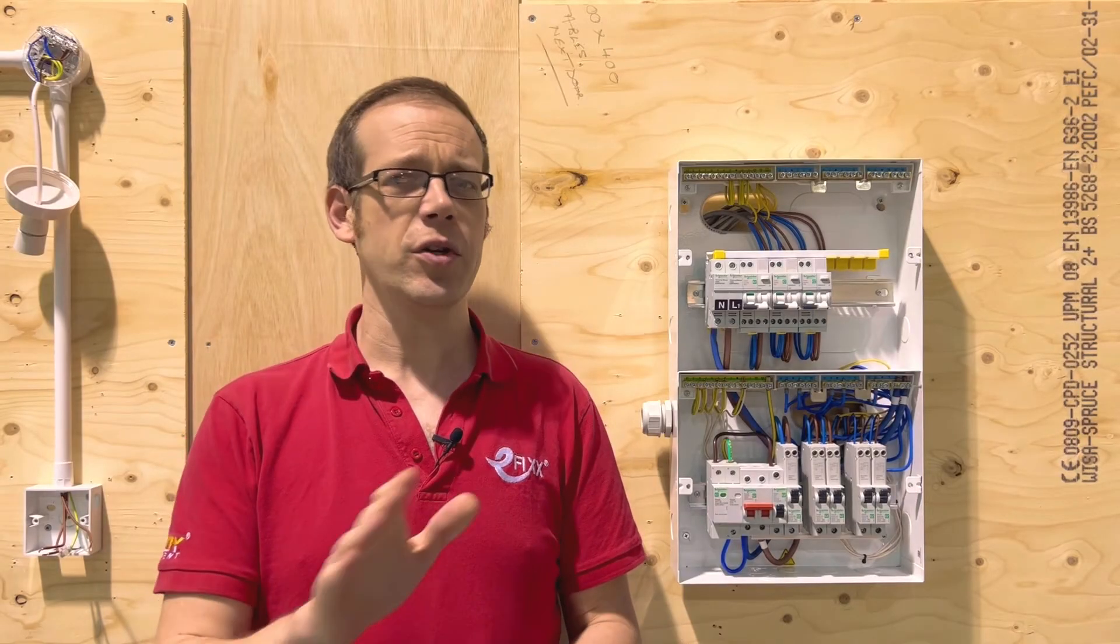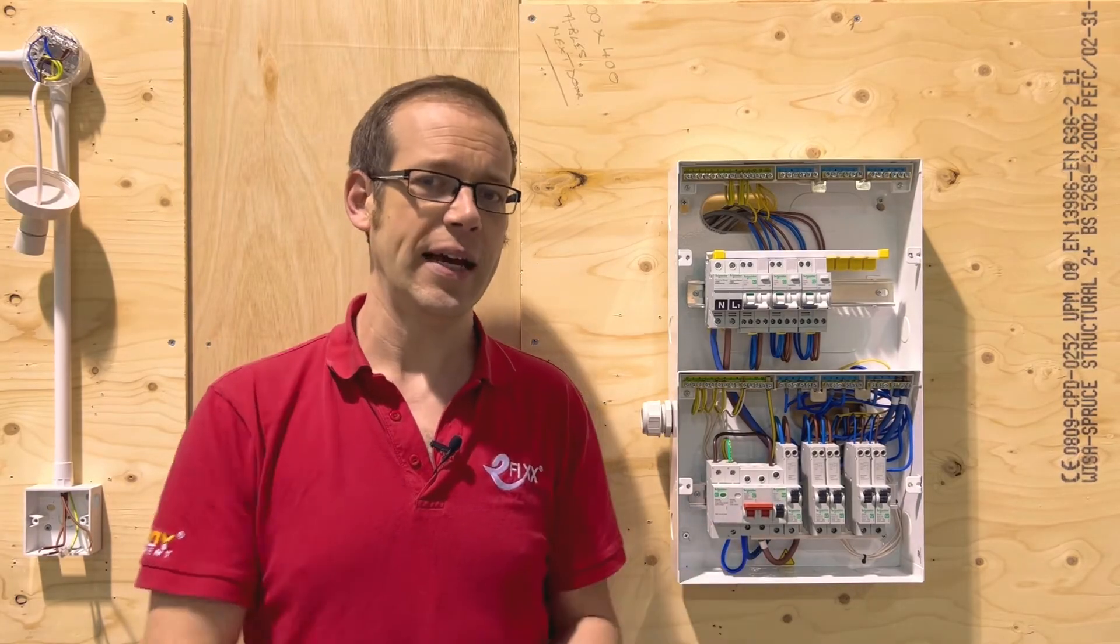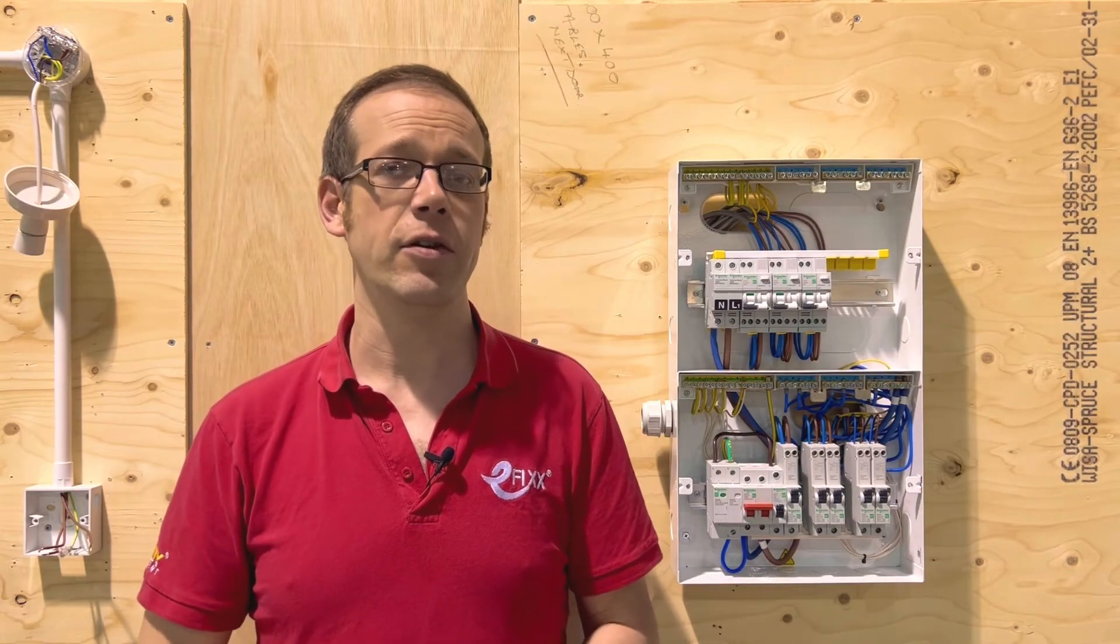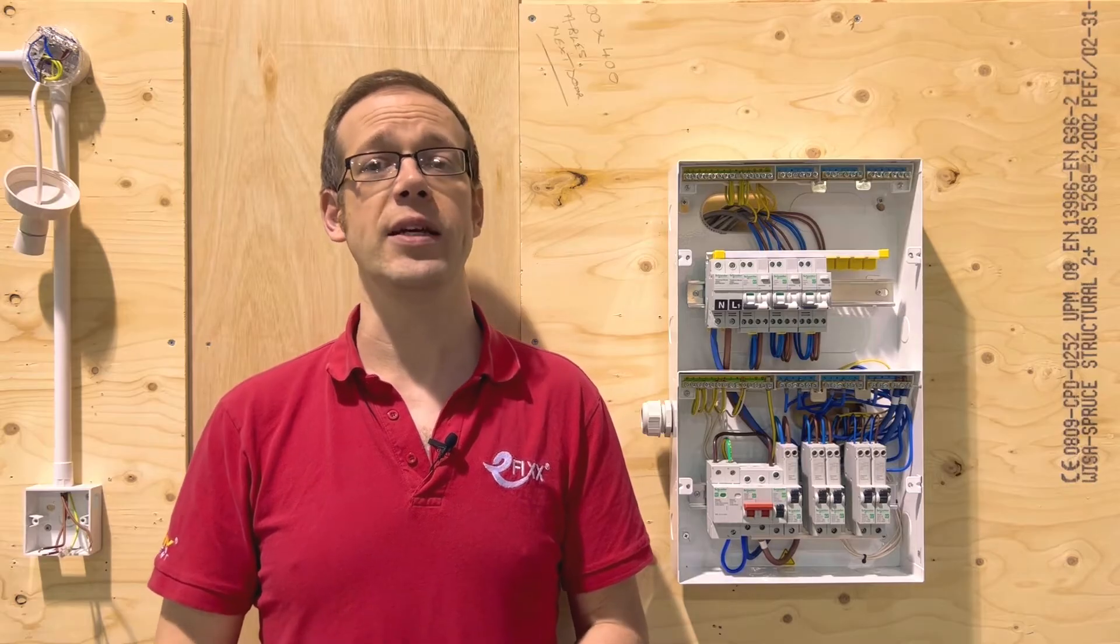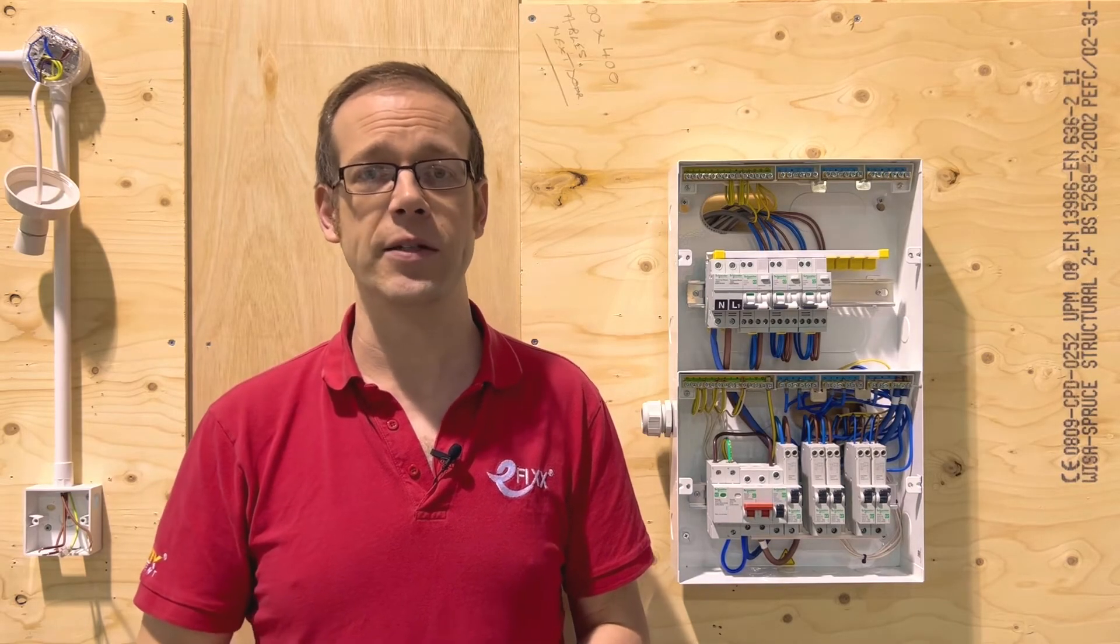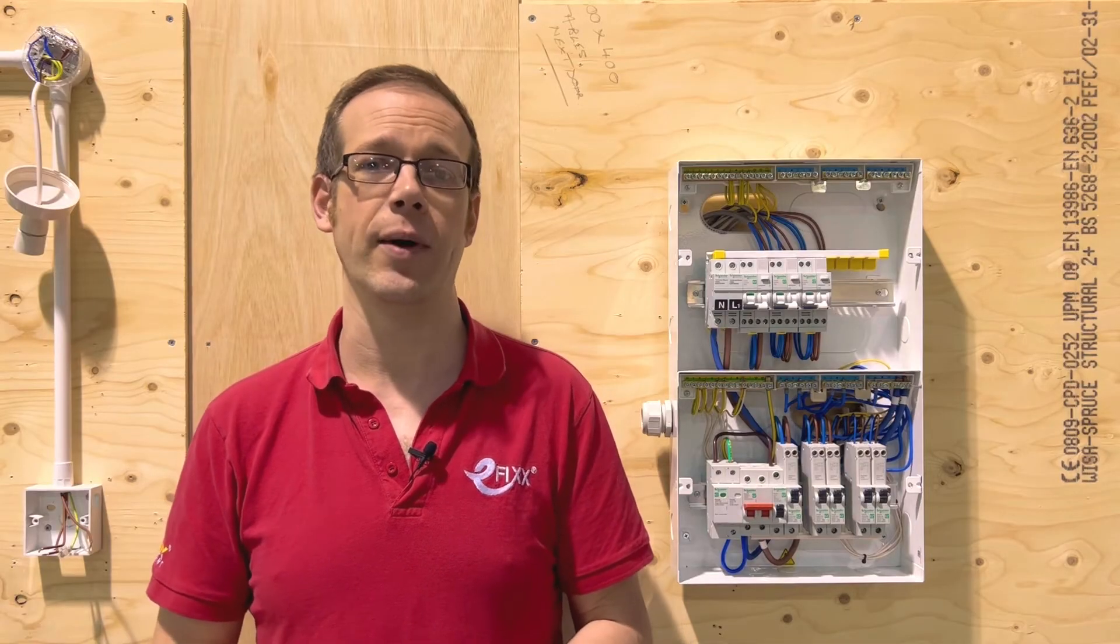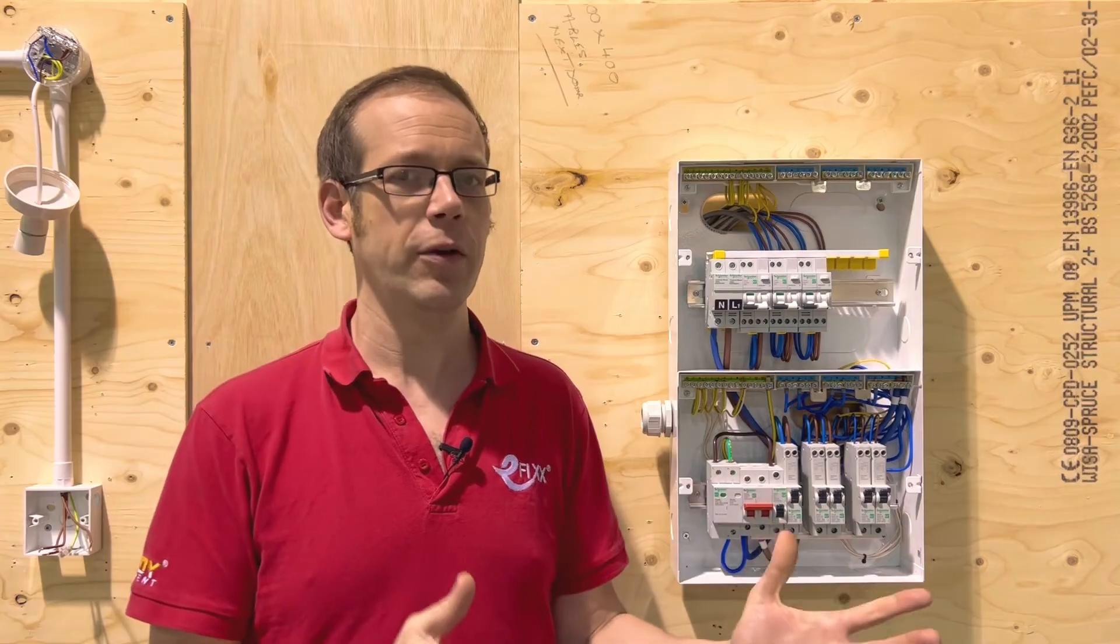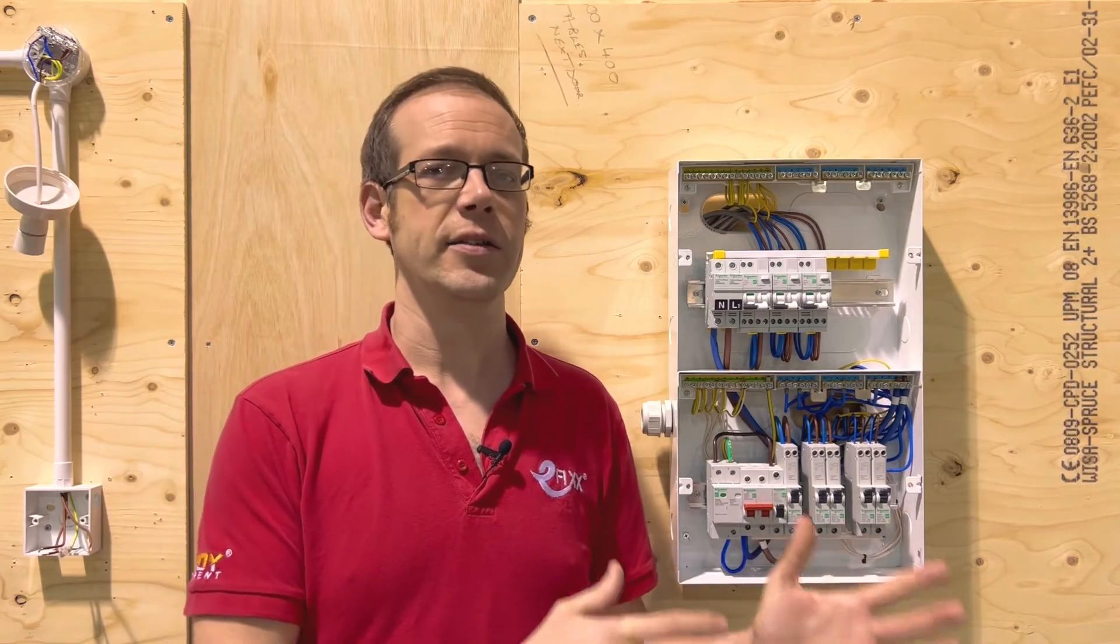So do socket circuits in other environments need AFDDs? Well the regulation continues for all other premises the use of AFDDs conforming to BSEN 62606 is recommended for single phase AC final circuits supplying socket outlets not exceeding 32 amps.